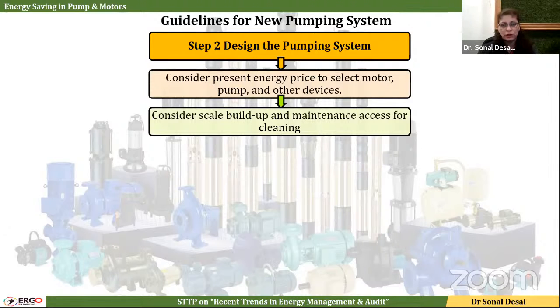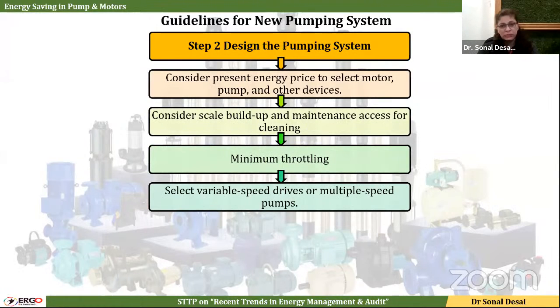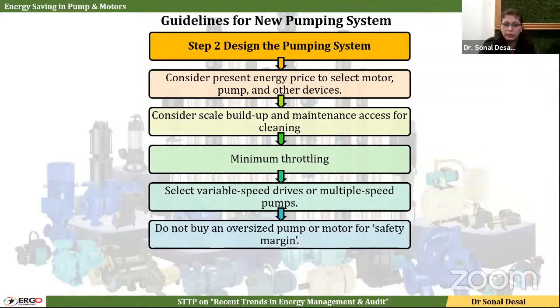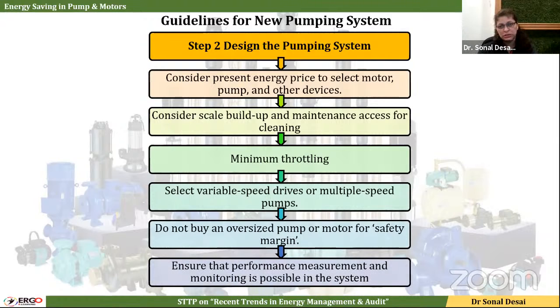Normally, oversizing is done to meet future requirements. Don't do it. Don't consider scale buildup. Rather than that, go with cleaning of the pipeline and maintain it so that cleaning will be there. There should not be throttling. Select a variable speed drive or a multi-speed pump, and never go for an oversized pump for a safety margin. You don't need a safety margin in a pump.